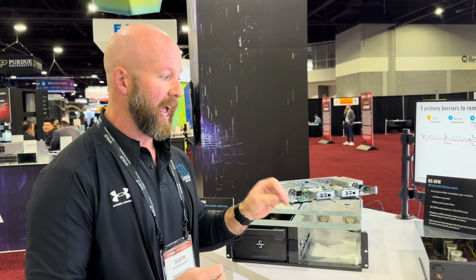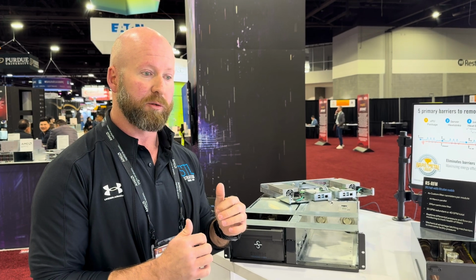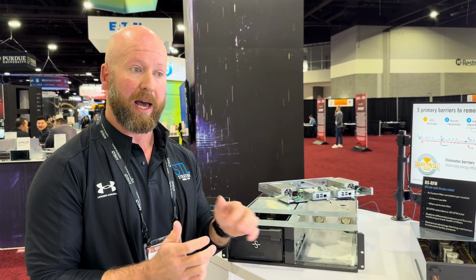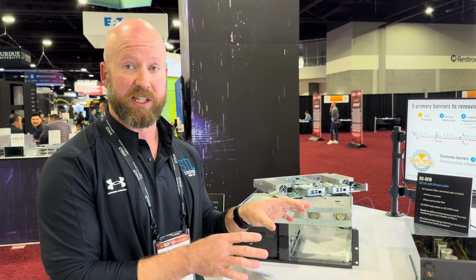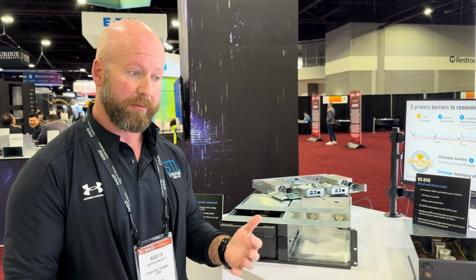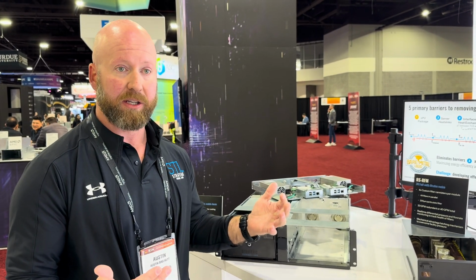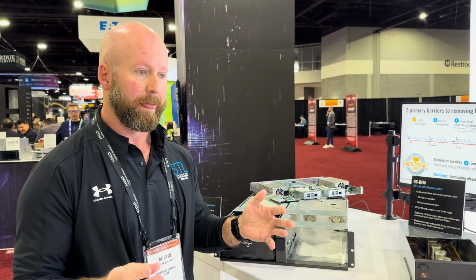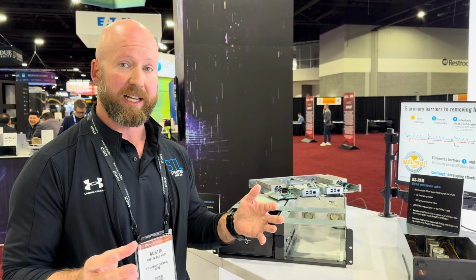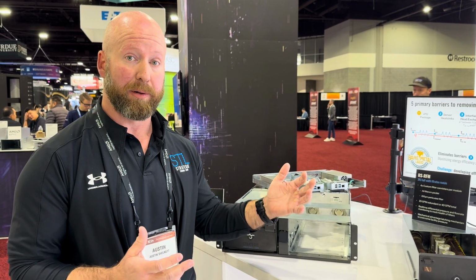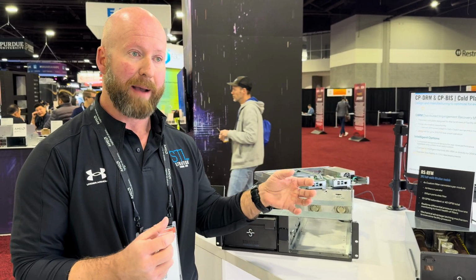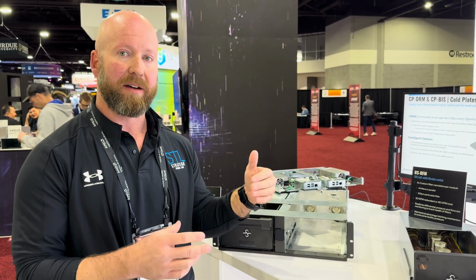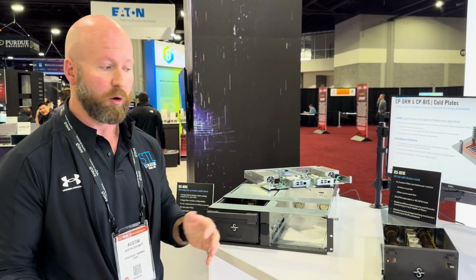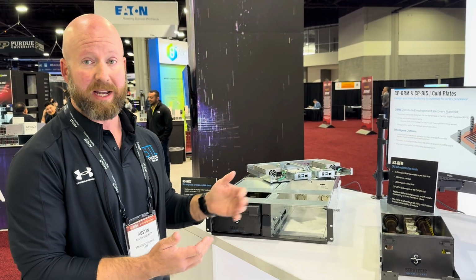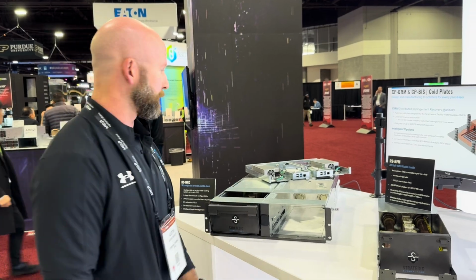Expectation is that we've designed the filters and the channels of our cold plates large enough that most buildings won't have any trouble filtering their water supply below the point where these devices wind up capturing a lot of particles. However, there's going to be, in many cases, some startup issues where a building has built their pipelines maybe in advance of deploying their liquid cooling solution, and those pipes, if they sit stagnant for a long period of time, might have some scale that breaks loose initially, winds up in the filters, you replace the filters, and then probably never again over the lifetime of the product.